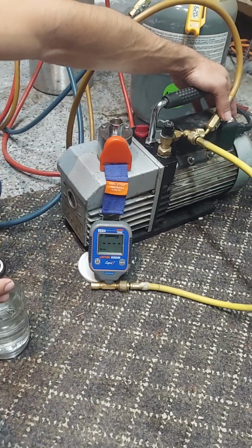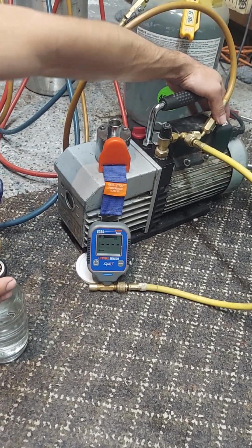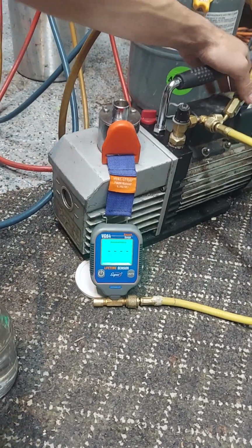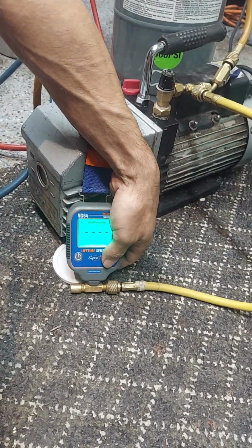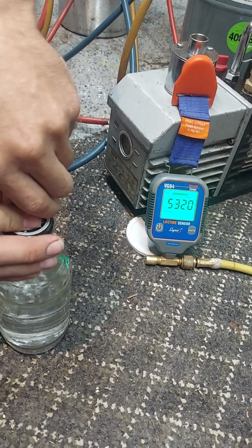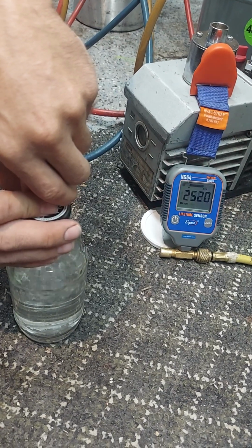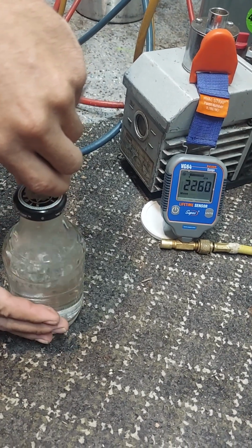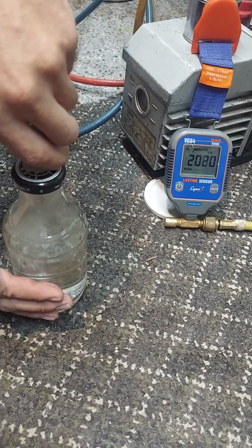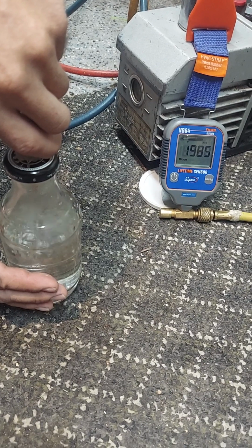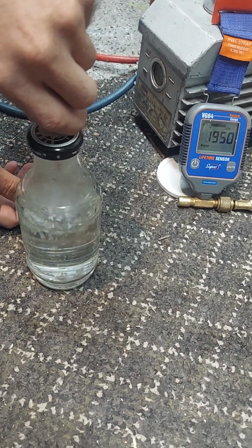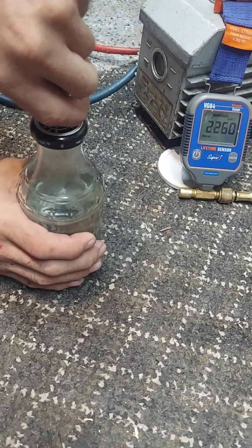Right now I can take the water and let's see how many microns it takes to boil it. Let's see if we can get the backlight on. Okay, here we go. I'm going to start it up. And we are boiling water. That's basically room temperature at, I don't know, 1900 microns. It's boiling pretty good, and that's probably about 75 degrees.